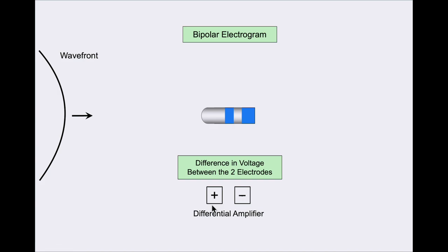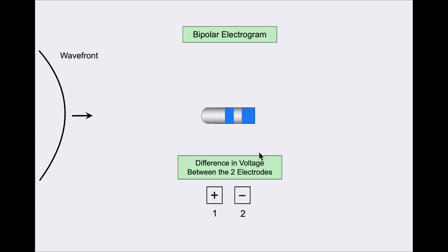For an ablation catheter, we always want to plug in the tip electrode or electrode one into the positive input, and then put the ring electrode or electrode two in the minus input. By convention, when we have a multi-electrode catheter with four, ten, or twenty electrodes, we follow the convention with the distal electrode plugged into the positive. So we would plug electrode three into the positive, electrode four into the minus, electrode five into the positive, electrode six into the negative, and so on.